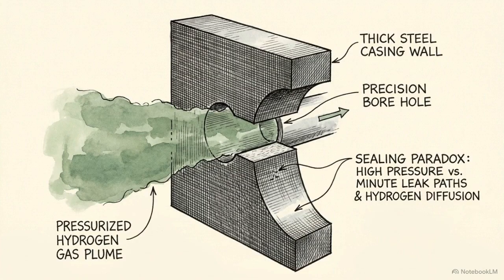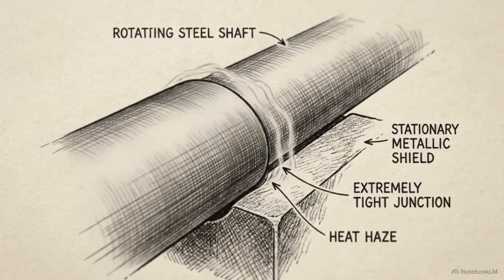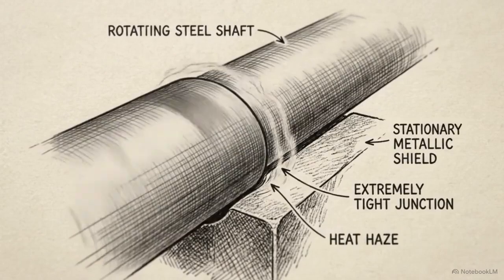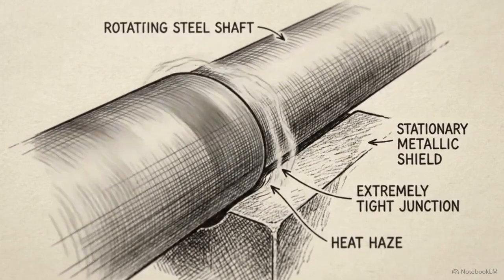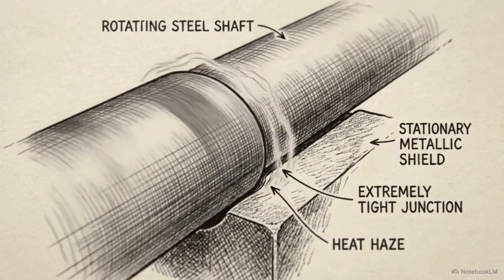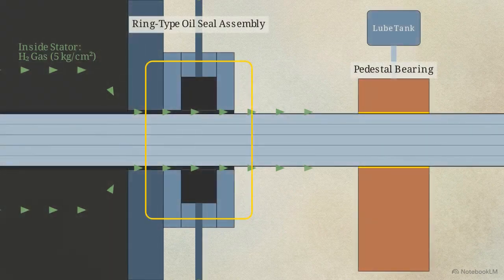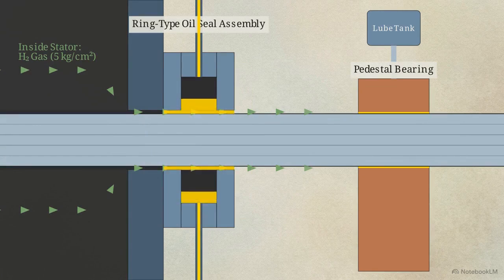Using pressurized hydrogen presents a critical sealing paradox. The gas fills the stator casing, but the rotating shaft must physically pass through the external shields, creating a massive potential leak path for explosive gas. The yellow path shows the mechanical solution. The generator uses hydrodynamic pedestal bearings paired with forced pressure ring-type oil seals. Oil is pumped into a pressure chamber at the external shield, forming a physical liquid barrier continuously blocking the hydrogen from escaping.